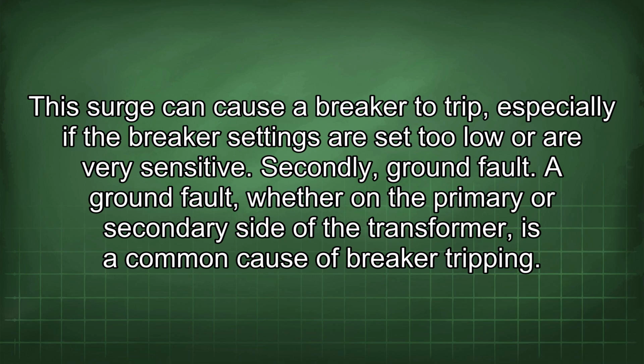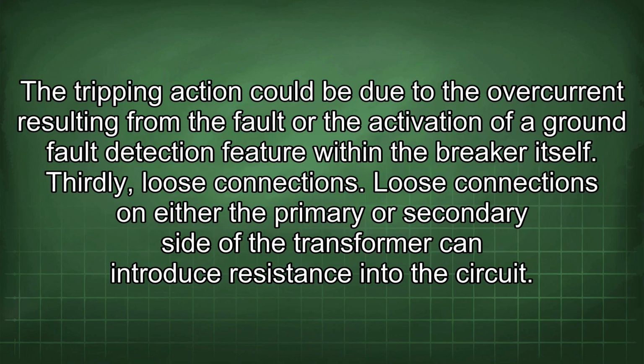sensitive. Secondly, ground fault. A ground fault, whether on the primary or secondary side of the transformer, is a common cause of breaker tripping. The tripping action could be due to the overcurrent resulting from the fault or the activation of a ground fault detection feature within the breaker itself.